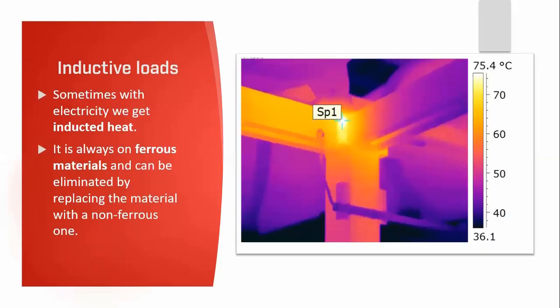In electricity we exploit induction, particularly in transformers using mutual induction. However, with so much AC electricity it's not unusual to find unwanted inducted heat on metalwork located near electrical components. Induction will take place on metalwork, and while it can be difficult to establish the exact reason, it occurs as a result of the location and proximity of the metal to the electricity. Poor design of electrical panels can create quite phenomenal induction patterns.